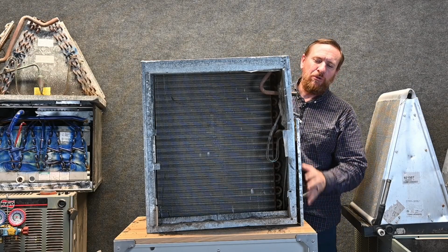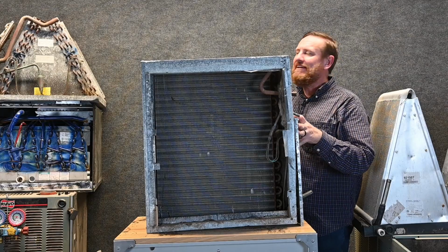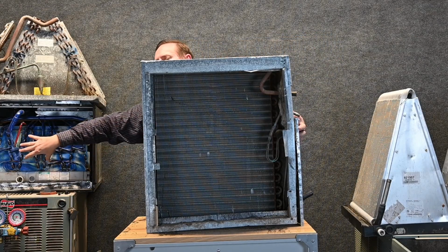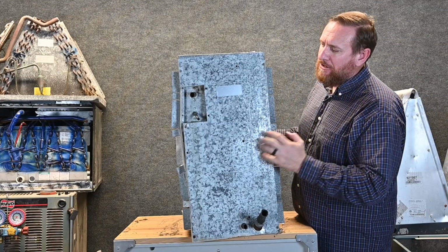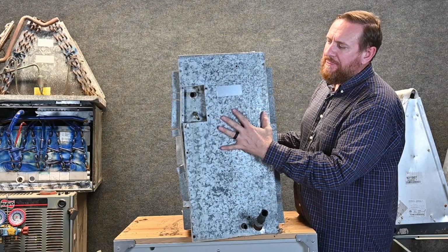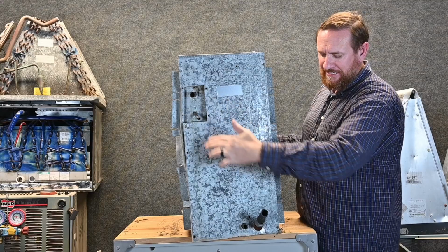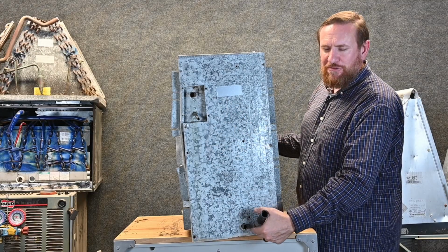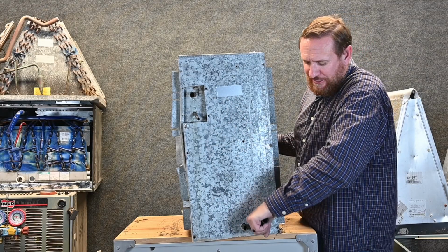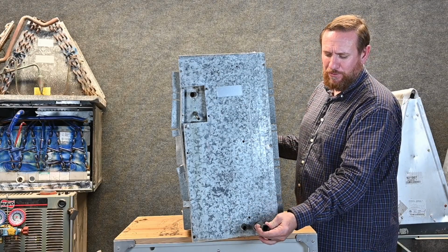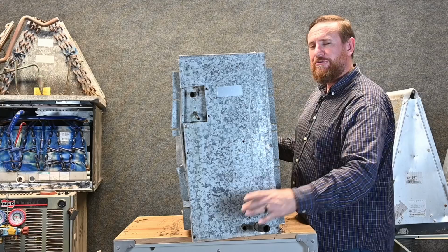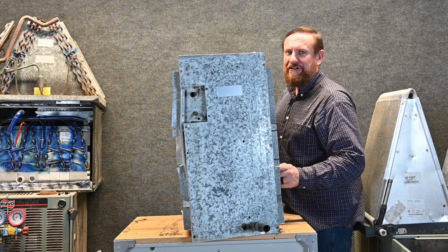I like these old coils because they didn't restrict near as much airflow as some of these very compact coils that we see today. When you come up to a slab coil, you won't see that. All you're going to see is a panel like this. This is our access panel, suction side, liquid side, and also we have our main drain line and our auxiliary drain line. This one had a metal drain pan that was completely shot, and some really poor and horrible drain lines, and we'll talk about drain lines in another video. There's so much to learn.